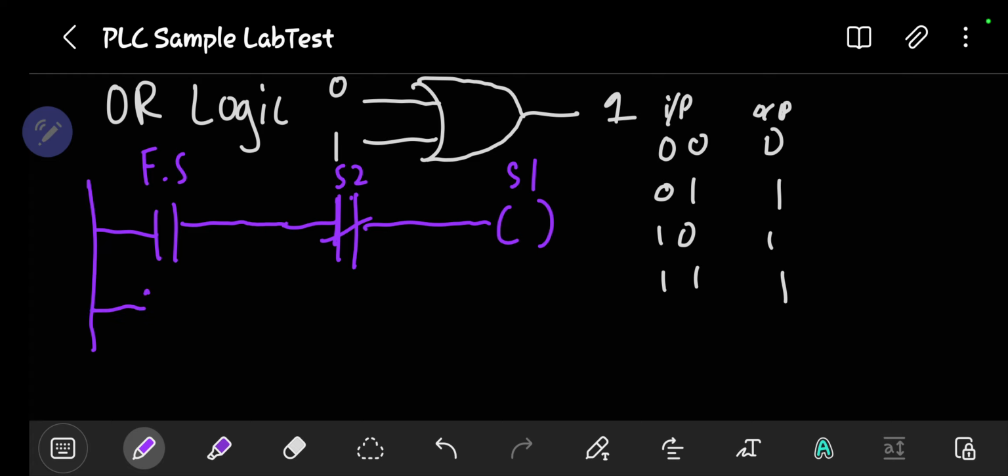So we say we need to latch it. So this is S1 again, right? What happens now is that when my first scan is on for one scan cycle, it quickly turns on my S1. My S1 turns on, and then it causes this latch to become an NC latch, and now current can flow in this path instead. It's an alternate path.